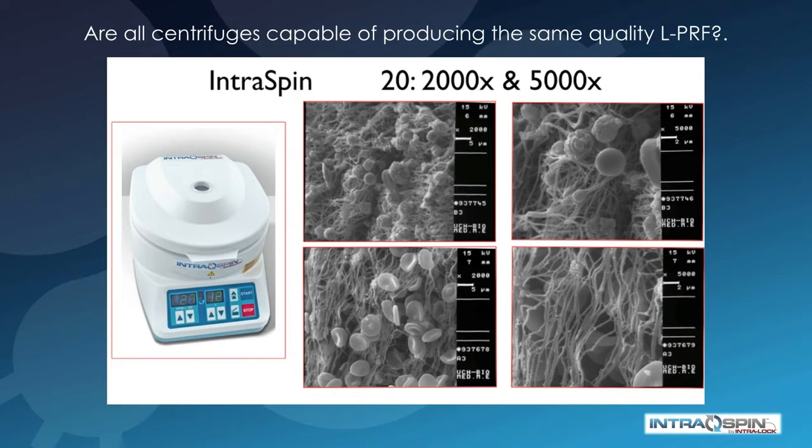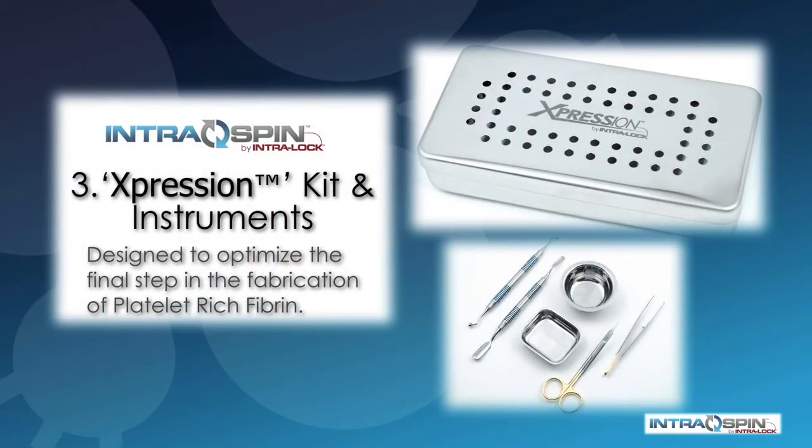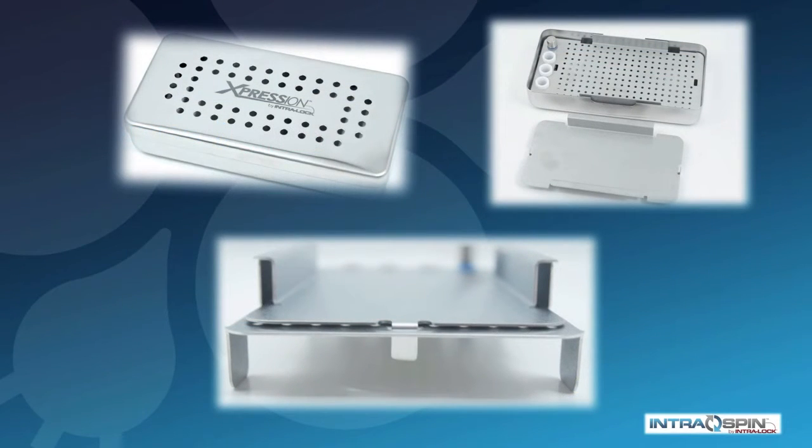This is important because biologic efficacy is directly related to the number of vital cells. Finally, the heart of the IntraSpin system is the Xpression box and the instrumentation kit, designed to optimize the final step in the fabrication of PRF. The compression plate in this box guarantees that you will end up with membranes of a consistent thickness.